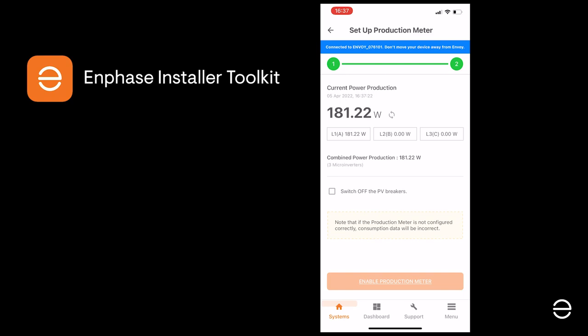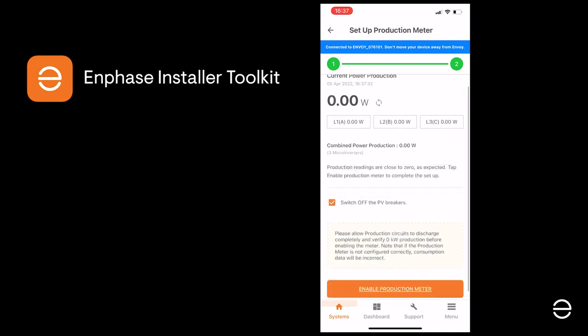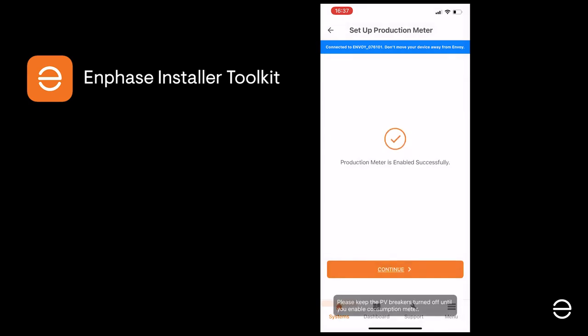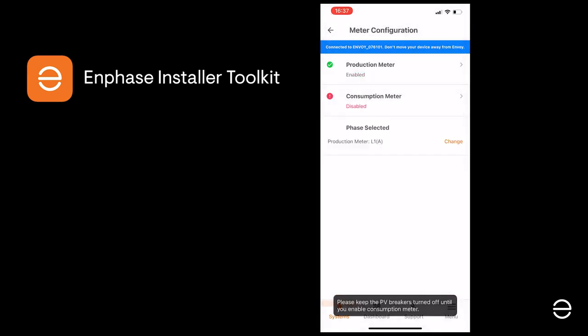The next step is to switch off the PV circuit breakers to check that the production is zero and the system is correctly configured. If that's the case, we can check the box and enable the production meter. Make sure you leave the PV breakers off for now.